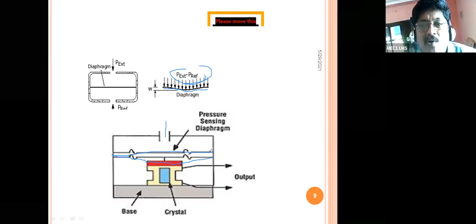When pressure is applied on a piezoelectric material, like natural crystals such as quartz or synthetic crystals, it undergoes a change in dimensions, or deformation, thereby producing electric current. Similarly here, we arrange a small pressure applied on the crystal. When pressure is applied, the diaphragm undergoes deflection, and that pressure applied on the piezoelectric crystal causes a change in dimension, a deformation. So we get the correct output. We can also use this thin membrane for other purposes.